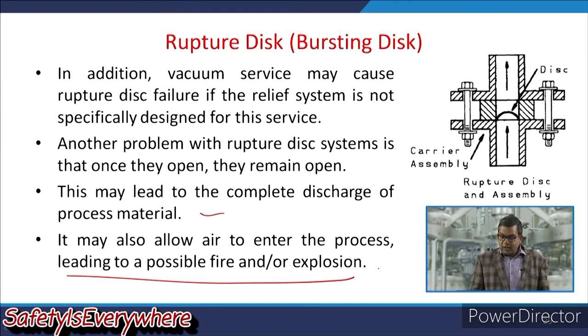Now sometimes to prevent this problem, rupture discs are available with embedded wires that are cut when the disc ruptures, and this can activate an alarm in the control room to alert the operator, so that they may be aware that the rupture disc has burst.